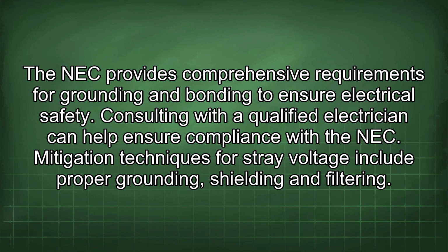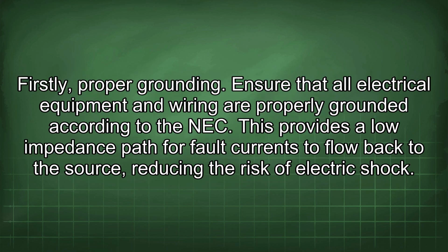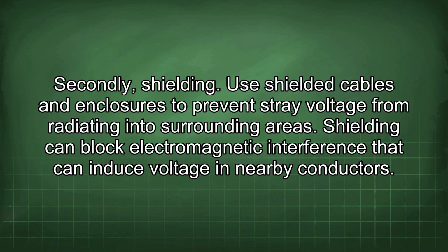Mitigation techniques for stray voltage include proper grounding, shielding, and filtering. Firstly, proper grounding. Ensure that all electrical equipment and wiring are properly grounded according to the NEC. This provides a low impedance path for fault currents to flow back to the source, reducing the risk of electric shock. Secondly, shielding. Use shielded cables and enclosures to prevent stray voltage from radiating into surrounding areas. Shielding can block electromagnetic interference that can induce voltage in nearby conductors.